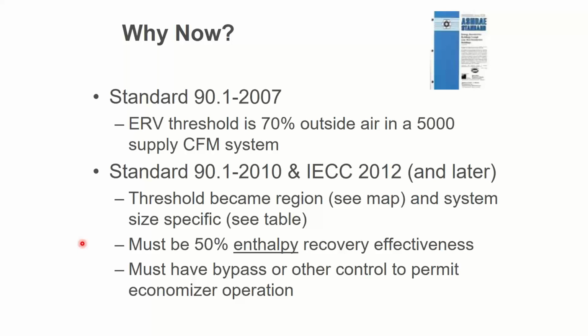And they've had this mapping system since the 2012 IECC. I'm going to show you the map here in a second. In addition to the map, you also need to have 50% enthalpy recovery, meaning sensible plus latent. And because runaround coils and heat pipes don't do latent, you can't get 50% total because you can't get it all from the sensible side. So you kind of have to use wheels and plates.